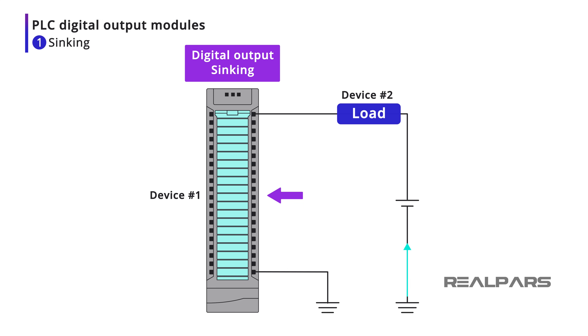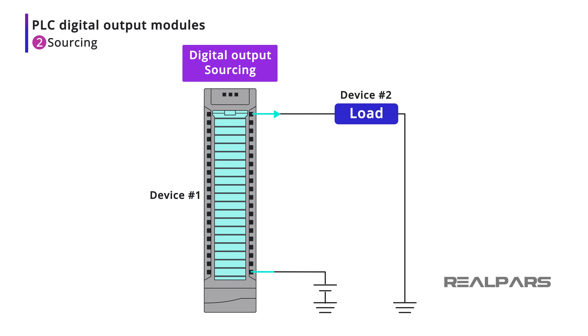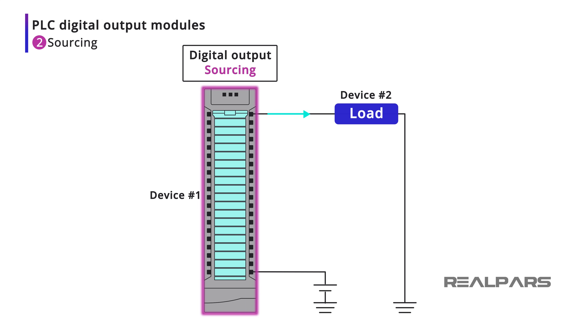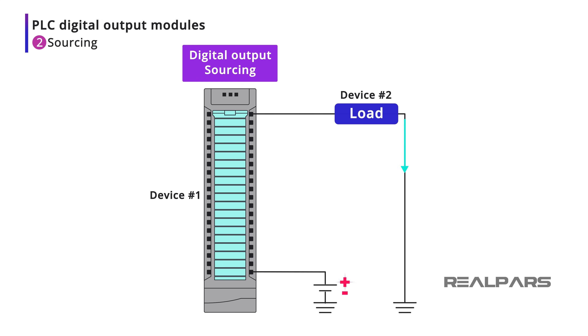Let's have a look at two devices with current flowing between them. One device is a PLC output module, and the second device is a relay. Based on the connection polarity, the sinking module will have the current flowing into it from the load. Now let's do that again, but this time one of our devices will be a sourcing module. Based on the connection polarity, the sourcing module will have the current flowing out of it and into the load.